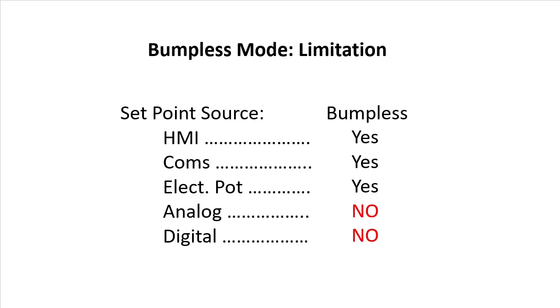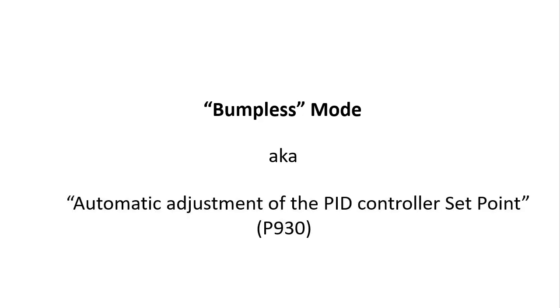And I should point out that I'm using the term bumpless because it's the most common term for this industry. But you won't find the word bumpless in the WEG programming manual. They prefer to call it Automatic Adjustment of the PID Controller Setpoint.